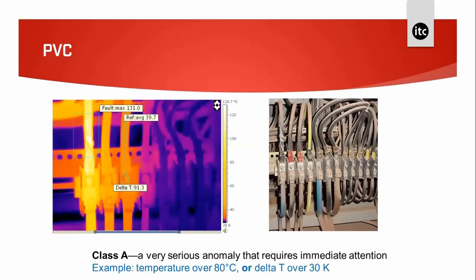In this case with PVC cable where the sleeving is burned off, we can see that gas ignited and damaged the insulation in the middle of the cable. The delta T in this image is 91.3°C, which pushes this into a Class A situation straight away.